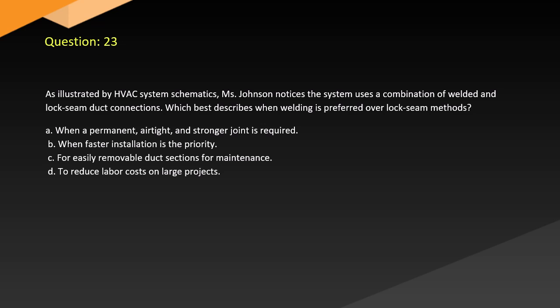Question 23. As illustrated by HVAC system schematics, the engineer notices the system uses a combination of welded and lock seam duct connections. Which best describes when welding is preferred over lock-seam methods? A. When a permanent, airtight, and stronger joint is required. B. When faster installation is the priority. C. For easily removable duct sections for maintenance. D. To reduce labor costs on large projects.